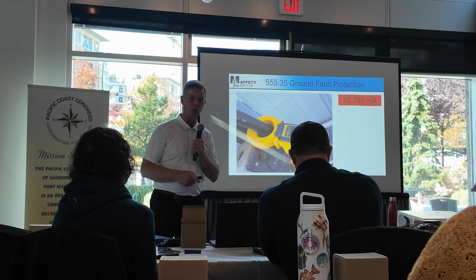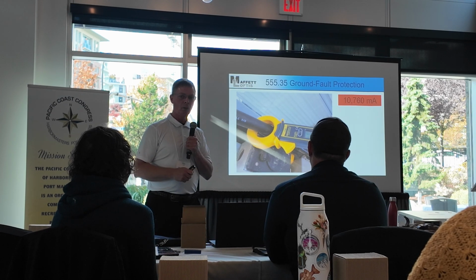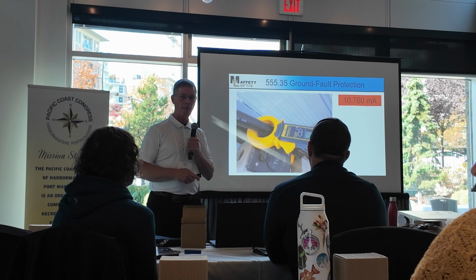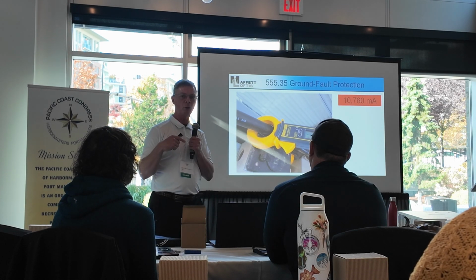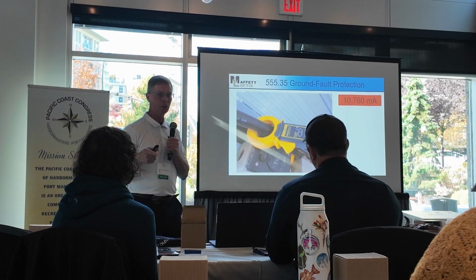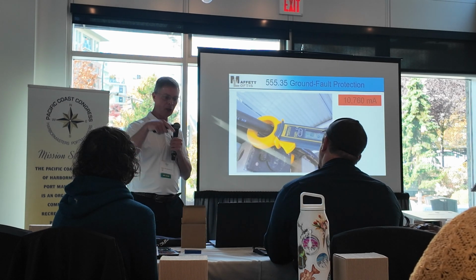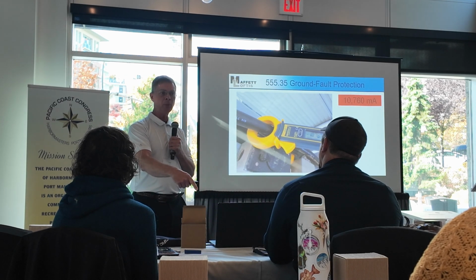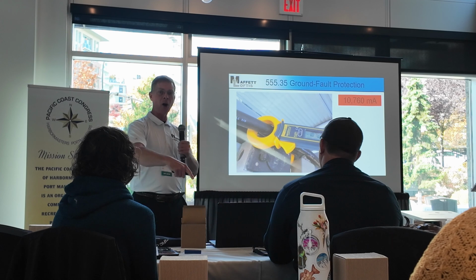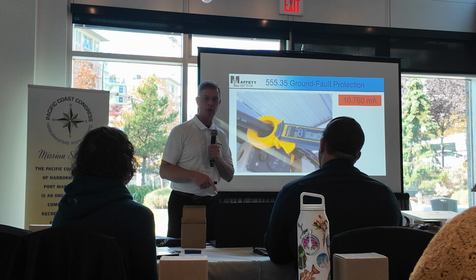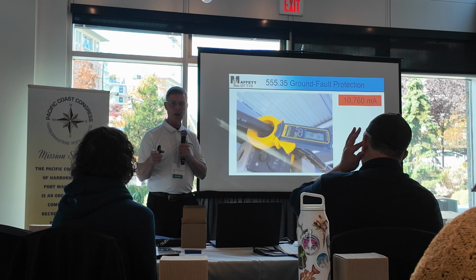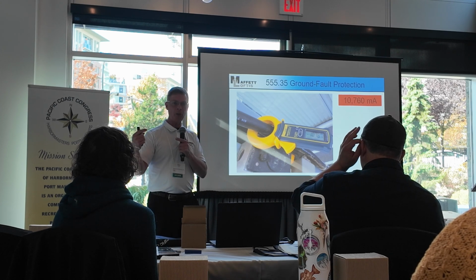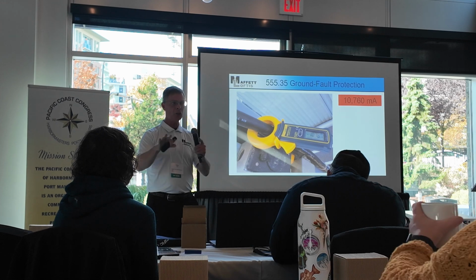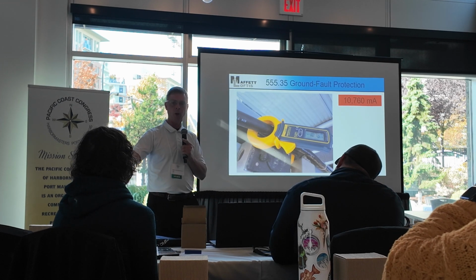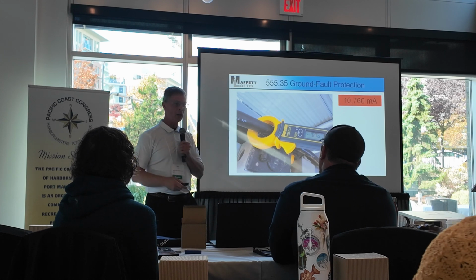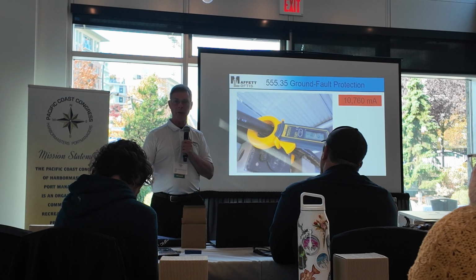I don't care if you stick your big toe in the water, you're electrocuted around this boat. No kidding. I mean, at that stage, is it completely miswired? Now, what happened here is this was a boat that was winterized. He didn't want to winterize his boat, so he took the dipstick out of his engine and put a 120 volt heater down into his engine block. And sometime over the winter, with all the movement, the 120 volt heater shorted out against the engine block, and it had a very poor grounding system. It actually arced and disconnected the grounding system when it had fault current, energizing every single piece of metal on his boat, including the aluminum hull. And it was leaking about 11,000 milliamps and he wasn't there.